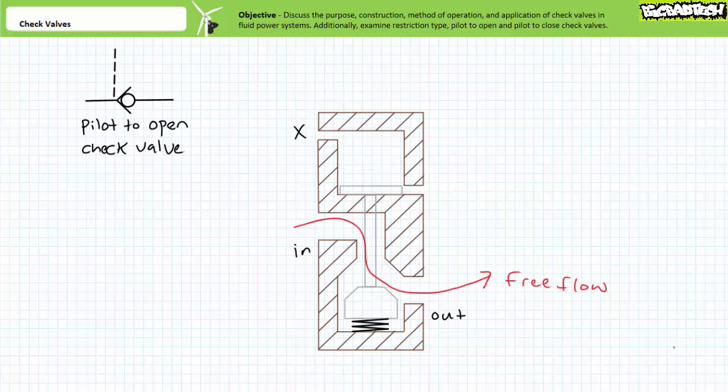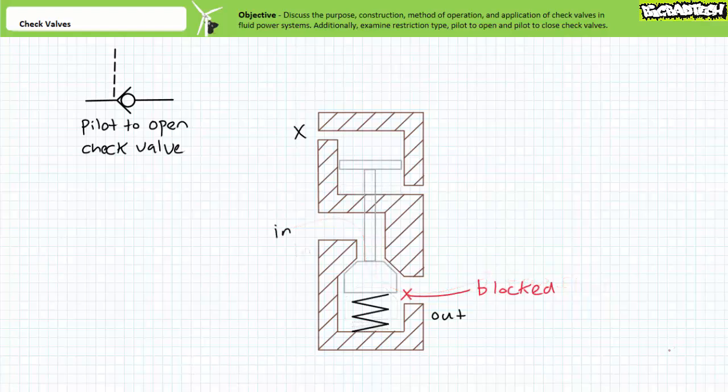In the absence of pilot pressure, the pilot to open check valve acts just like a regular check valve. In the free flow direction, the poppet is forced off its seat and fluid flows unrestricted through the valve.